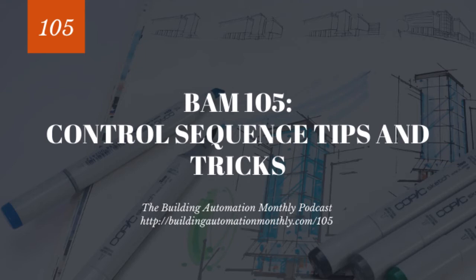Now, some actual commissioning agents, not all, but some, hold you to the letter of the law, and I see this. Oh, do I really want to say this? I see this on LEED projects a lot, where commissioning agents get selected because of their experience on LEED projects and not their actual knowledge of how stuff works. And so I see some commissioning agents who have no clue what's going on, and they read a sequence of operations, and they read it literally, and then they say, well, you had to open the isolation valves before you turn the chiller on. You failed the sequence. And it's like, really, dude? Really? I mean, do you know how this stuff works?